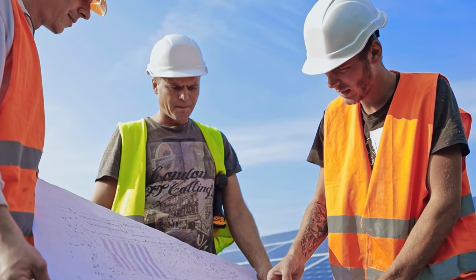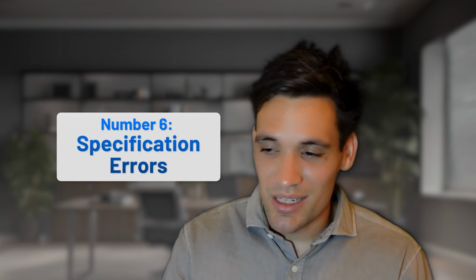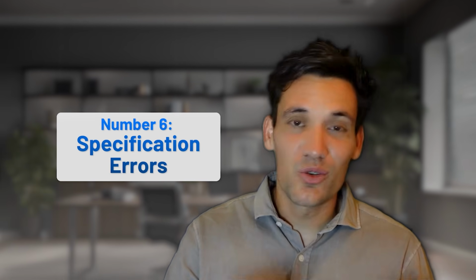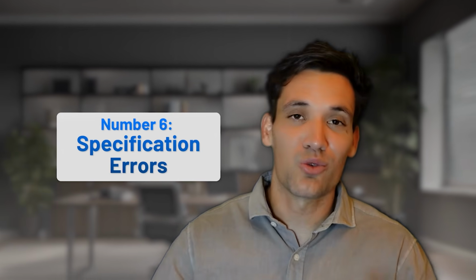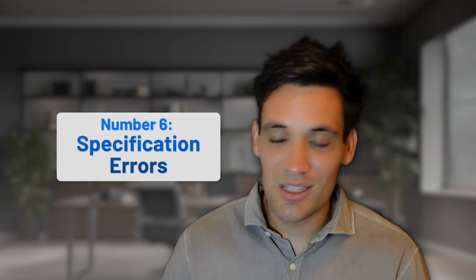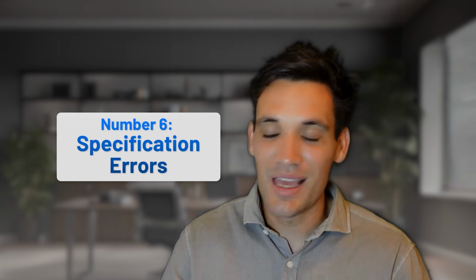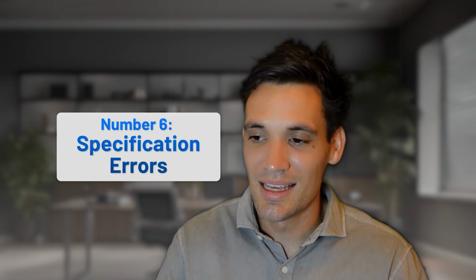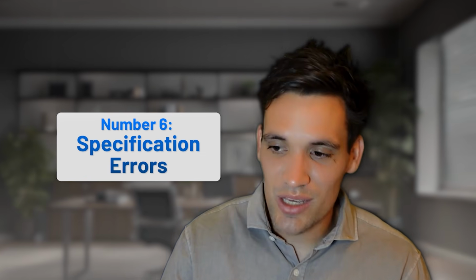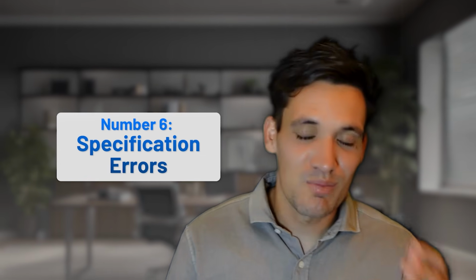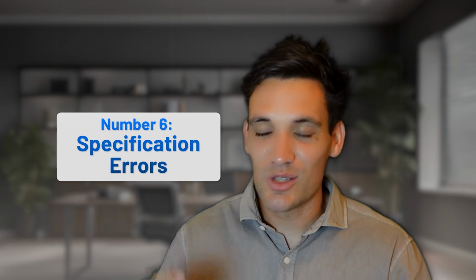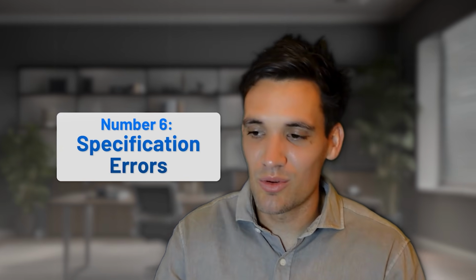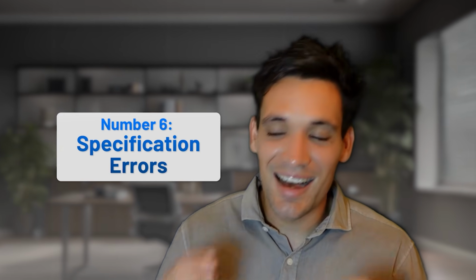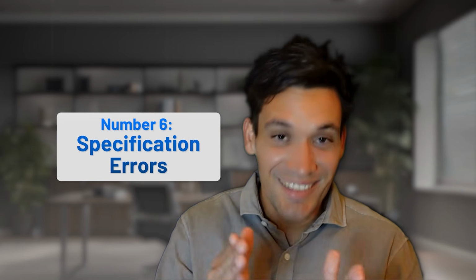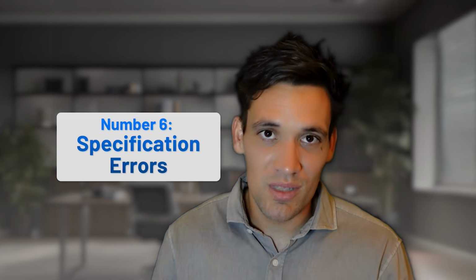The types of problems I've seen: incorrect IP ratings of equipment, incorrect UV protection of cables, having to go through a whole solar farm and install additional mechanical protection because the cables we ordered weren't UV rated, inconsistencies with phase rotations, metric versus imperial sizing, missing certifications that the inspector won't approve. All these minor errors aren't picked up until the late stage of the installation and moving into commissioning.